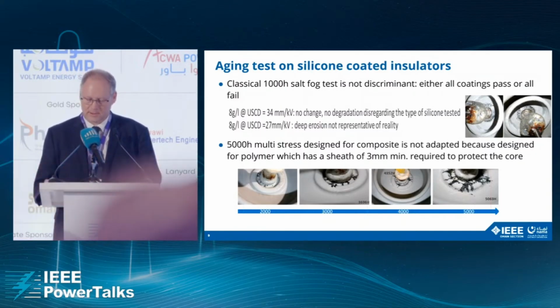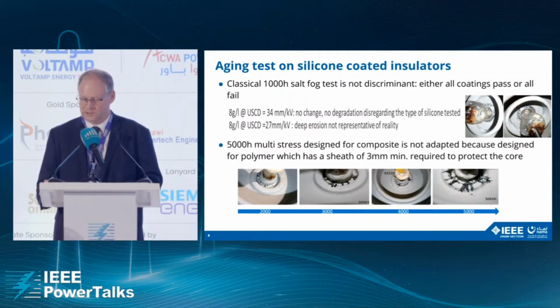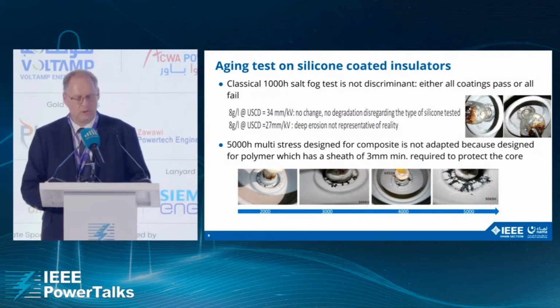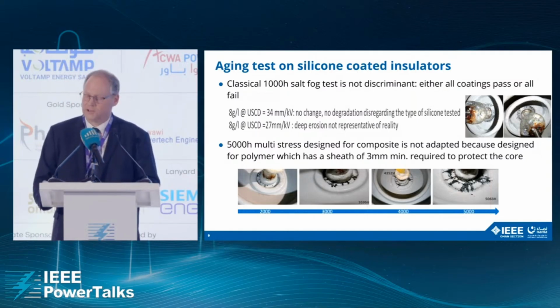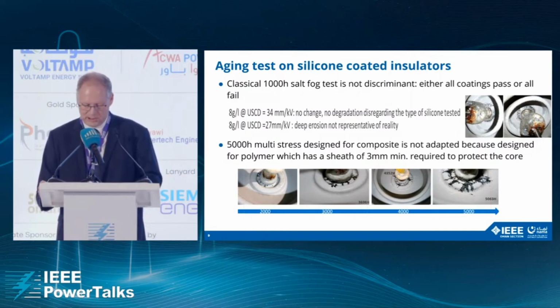First, the 1000-hour salt fog test described in the IEC 62217. This test depends largely on the USCD, what we call the Unified Specific Creepage Distance that is being used, and on the insulator profile. The second test is the 5,000-hour multiple stress test described in the IEC 62730. But both tests are designed for polymer insulators, which have a sheath of minimum 3 mm in thickness required to protect the core. But these tests are not designed to discriminate the performance of coatings, which are applied in thin layers, typically less than 0.5 mm.